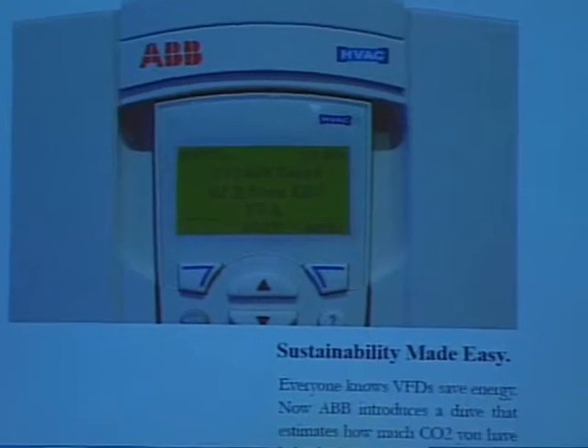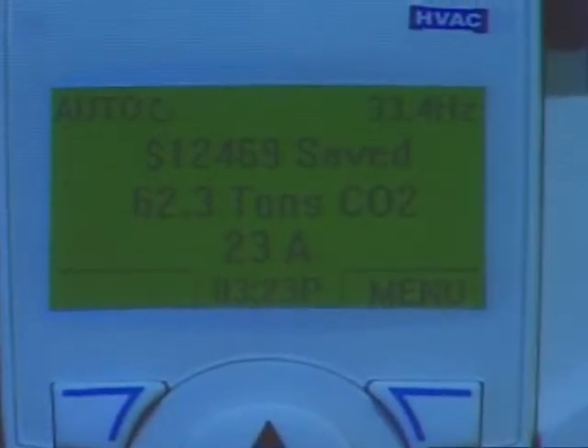The CO2 calculation is in the drive firmware, released in 2008. If the drive is older than 2008, you'd need to flash new firmware; if it's after 2008, it's already in there — you just go in and turn it on, your local rep can show you. One concern was that the CO2 factor is based on Wisconsin's roughly 80% fossil fuel electricity generation. For states like Washington with a lot of hydroelectric power, you go in and adjust the factor to make the tons of CO2 calculations more accurate.